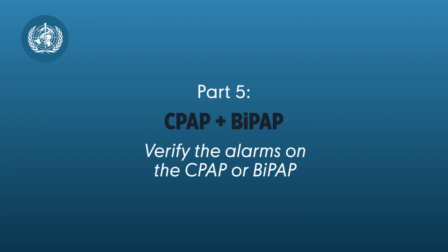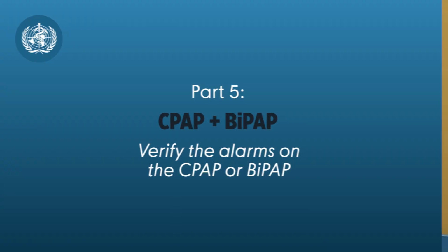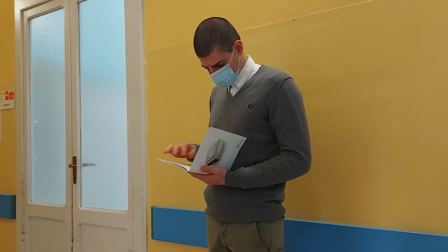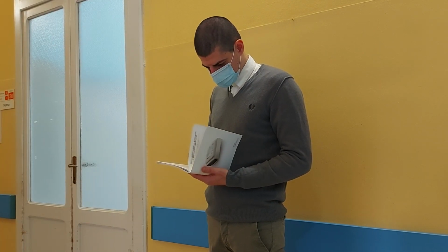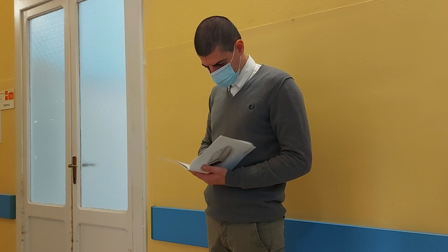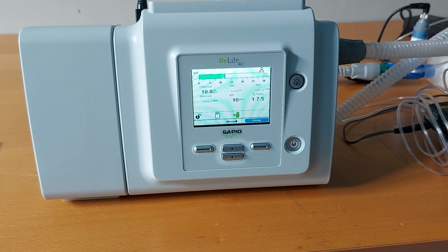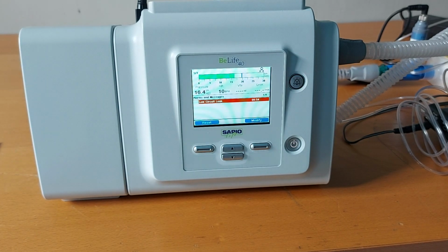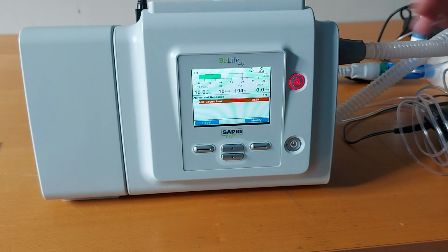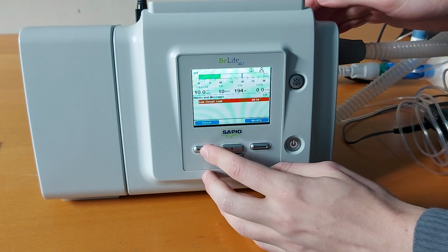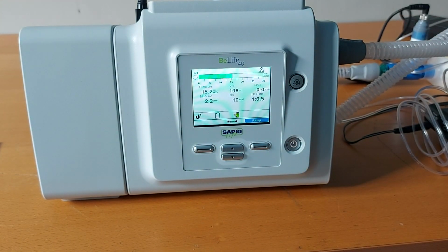Verify the alarms on the CPAP or BiPAP. Review the manual for how to test the alarms, and always follow the manual when it conflicts with these instructions. Not all alarm conditions can be simulated easily. Audible and visual alarms should be heard and seen, respectively, by clinical staff. If there is an alarm silence control, check that the reset feature works. Verify that remote alarms work properly.